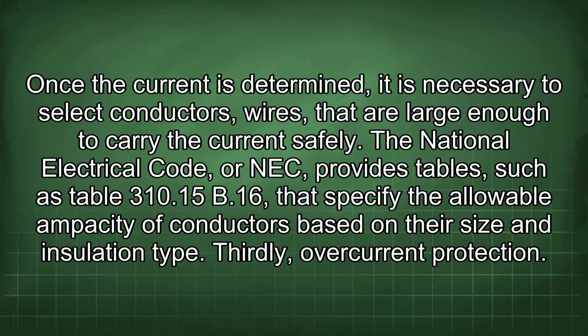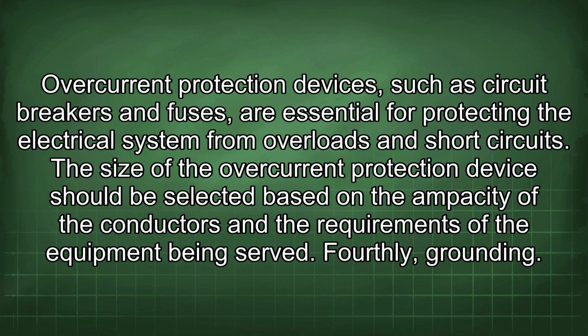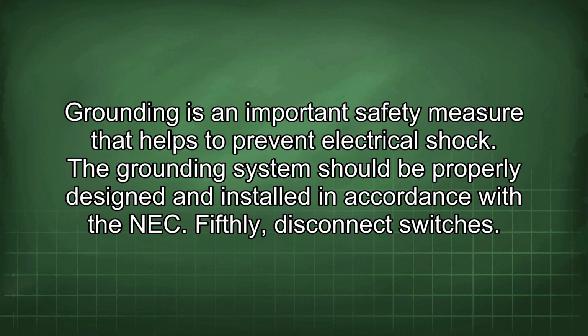Thirdly, overcurrent protection. Overcurrent protection devices, such as circuit breakers and fuses, are essential for protecting the electrical system from overloads and short circuits. The size of the overcurrent protection device should be selected based on the ampacity of the conductors and the requirements of the equipment being served. Fourthly, grounding. Grounding is an important safety measure that helps to prevent electrical shock. The grounding system should be properly designed and installed in accordance with the NEC.